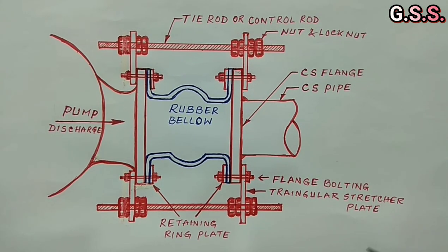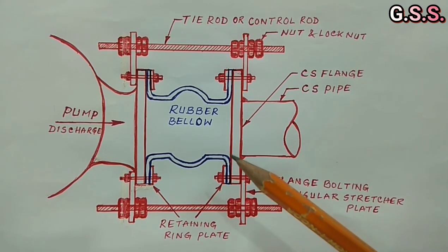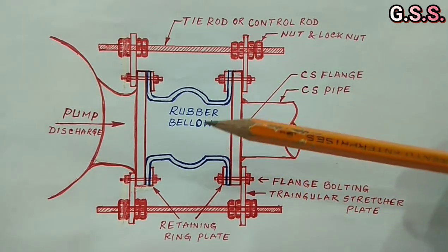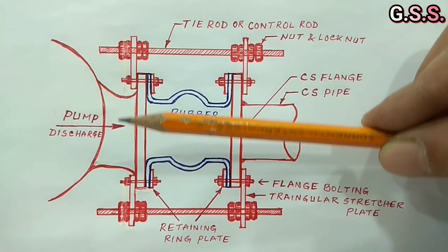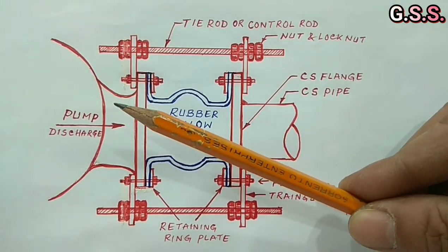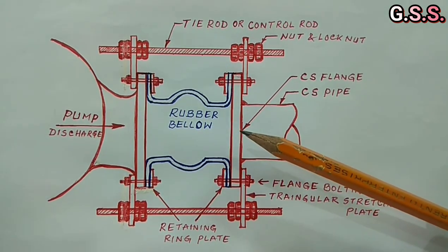So, to take care of this piping misalignment, we provide the rubber bellow. Rubber bellow is having flexibility in axial, lateral and angular direction and rubber bellow can take care of piping misalignment in any direction.